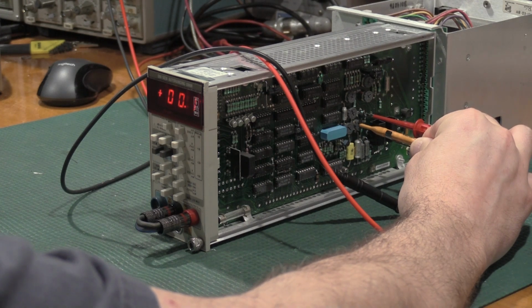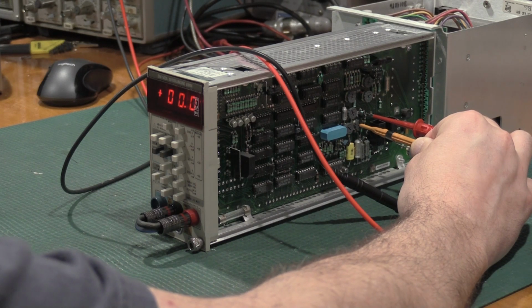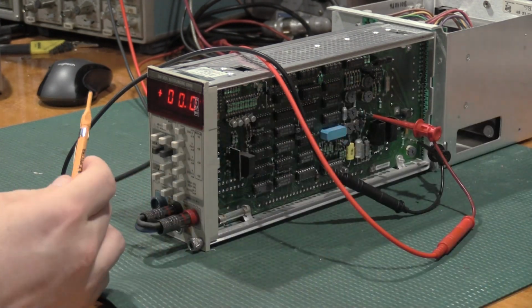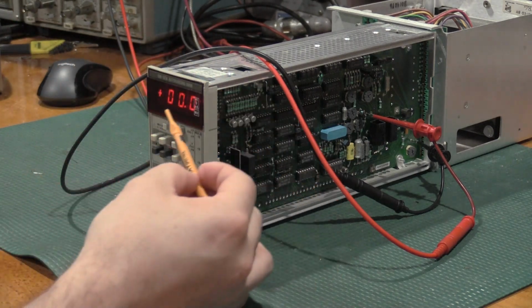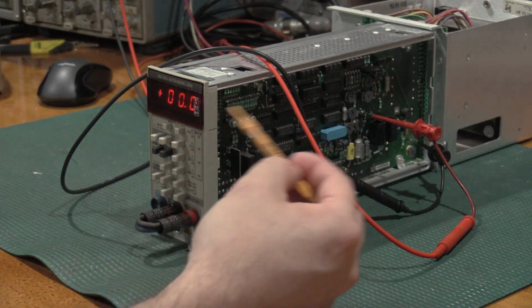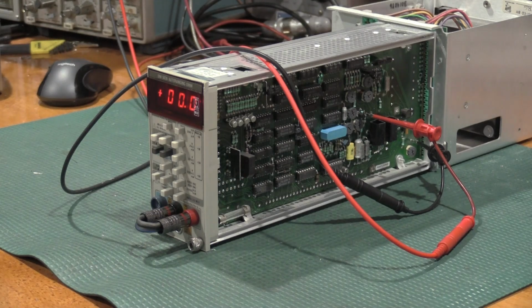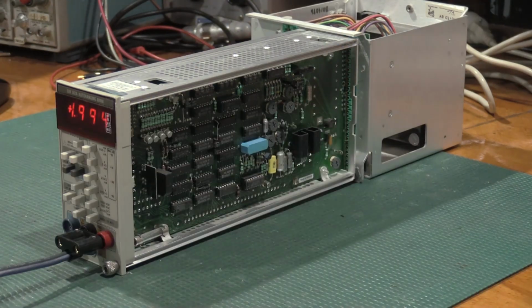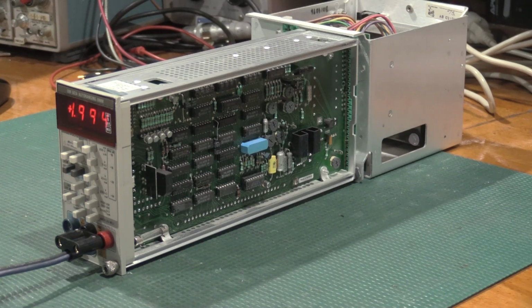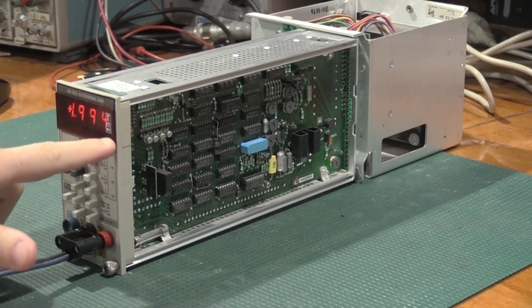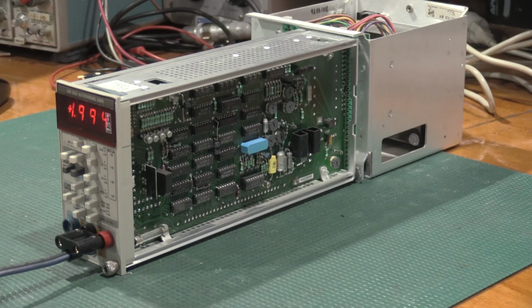All right, so we're at 1. So we'll go back half a turn, or half the space, to get it between +1 and -1 and -0.1 to +0.1, so it's right on in the middle of that range. That's a feel. It does not come through the camera very well. Okay, after waiting for a bit of ACAL on the meter to run, I have 2 volts on the calibrator. We're reading 1994. That's a little low. So that does need to be adjusted.